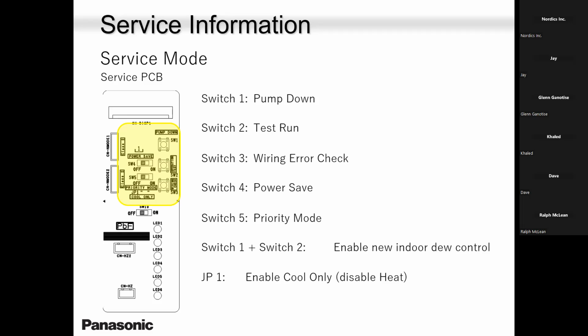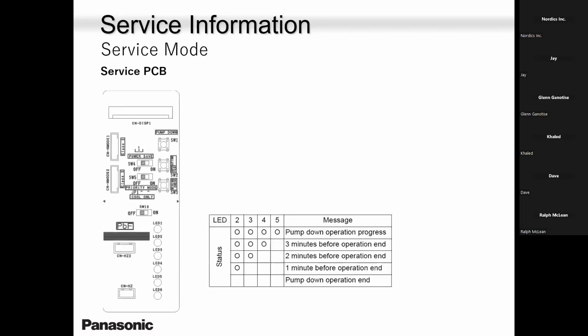Wiring check, please try your best not to use this feature. It can fix your wiring problems, but probably a temporary solution. I don't like it. So when you're done with your wiring and piping connections and flare and release of the gas and everything, and you're ready to run it, run one unit at a time, one indoor unit at a time in cooling, not in heating, in cooling. Make sure it cools well and not just blowing room temperature and another room is freezing. That means you have crossed your wires. So please test multi-zones, one unit at a time in cooling.